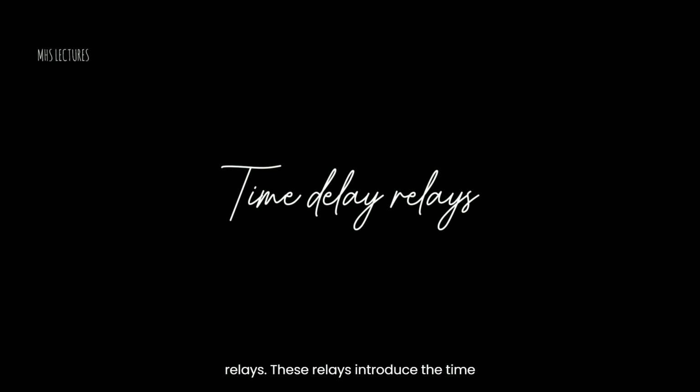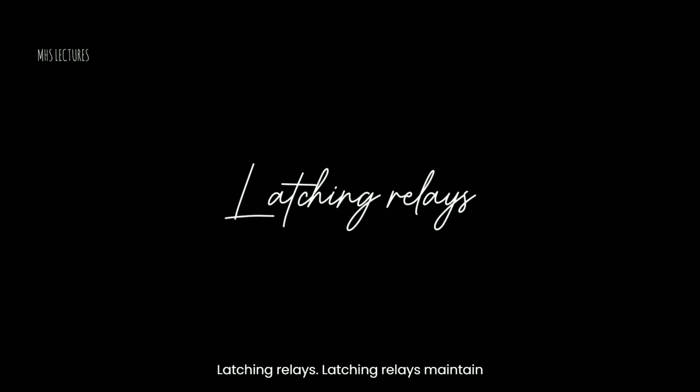Reed relays. Reed relays use magnetic fields to control reed switches, which are thin, magnetically sensitive metal strips that act as contacts. Time delay relays. These relays introduce a time delay before opening or closing the contacts, often used in applications requiring a specific time delay. Latching relays. Latching relays maintain their state even after the coil is de-energized. They require a separate pulse to change the state.